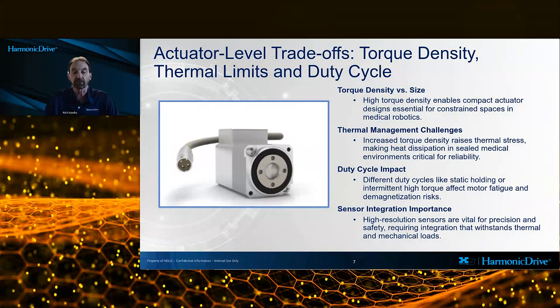Duty cycle further complicates the picture. Imaging systems may require long periods of static holding torque with minimal motion, which stresses motor windings and magnets thermally over time. Surgical robots, by contrast, may experience intermittent high torque bursts combined with rapid reversals, which can accelerate fatigue and demagnetization if not properly managed.